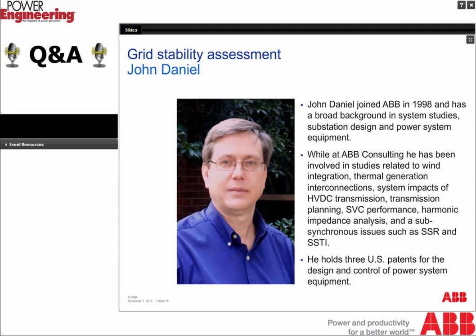Well, I think that if you are going to be considering the retirement of a unit, it's important to consider grid stability right away. The loss of the generating unit not only potentially impacts the voltage and the dynamic stability, but you're losing a whole slew of benefits that the generation is providing to the system, so it's important to study that early to know what the overall impacts to the network are going to be. If it's a utility that owns both the generation and the transmission, that gives them a good sense of what kind of reinforcements might be needed within the system.